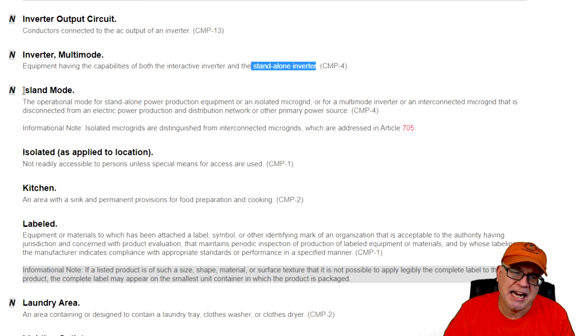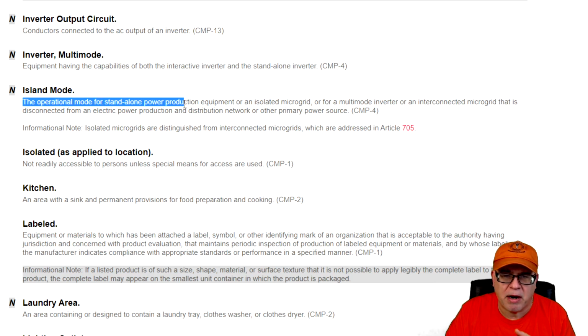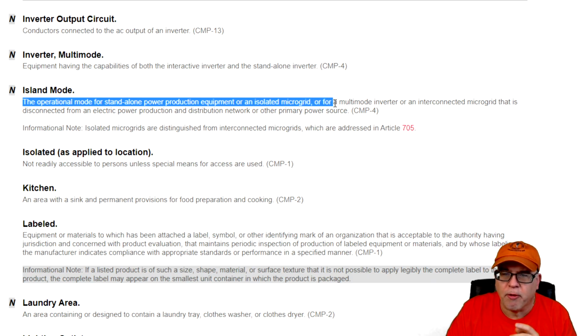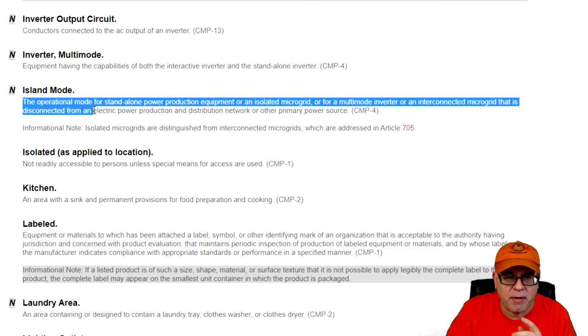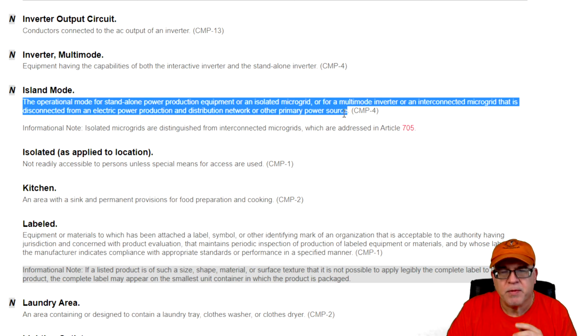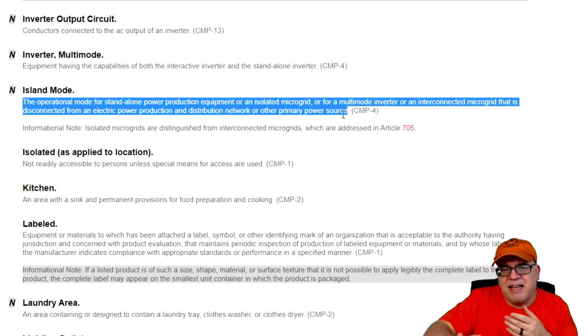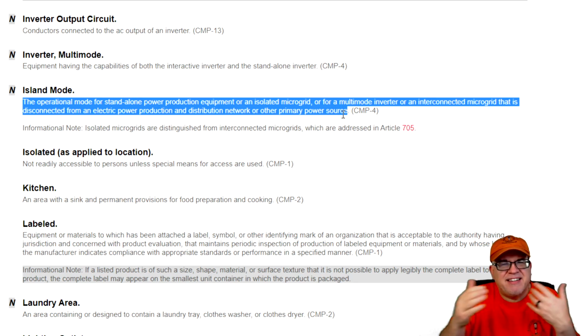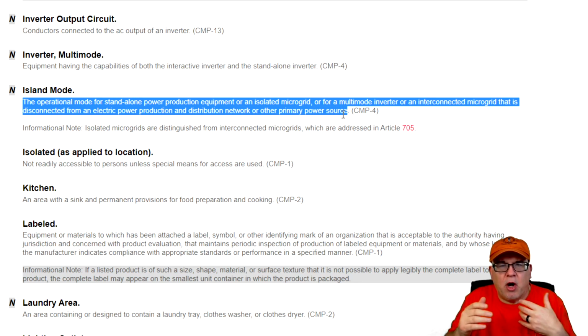Next, we have what's called island mode, and it is a specific operational mode. It says the operational mode for standalone power production equipment or an isolated microgrid. So we have a definition of microgrid when we get there. We'll talk about it. Or for multi-mode inverters or an interconnected microgrid that is disconnected from the electrical power production and distribution network or other primary power source. So it's connected away from it, or it can be isolated away. And so we used to refer to it as an isolation, and now we just call it islanding. Means it isolates itself out by itself, disconnects, still functions, but it's functioning in what we call an island mode.